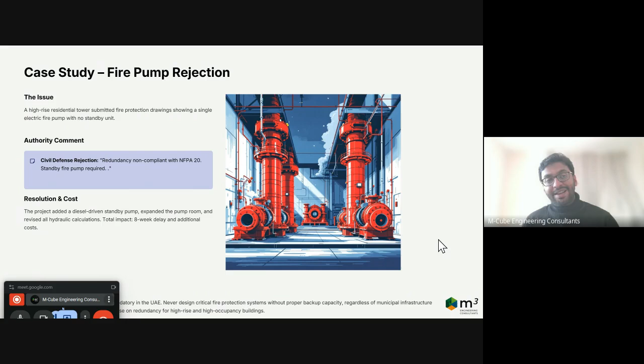It's a very simple thing: in the UAE it's not allowed to have only one single pump. This generally happens when the design is outsourced, when developers and clients aren't aware of local requirements and give the project to people unfamiliar with local codes, who design based on their own codes and requirements. No one reviews it, it's submitted to the authority, and it gets rejected. The whole project was delayed more than 8 weeks just because they missed showing the pump in the pump room. This creates awareness that all engineers need to know local codes and regulations, and outsourcing a project is not a solution. You need to ensure that even if it's outsourced, competent people are designing and reviewing it before submitting to the authority.